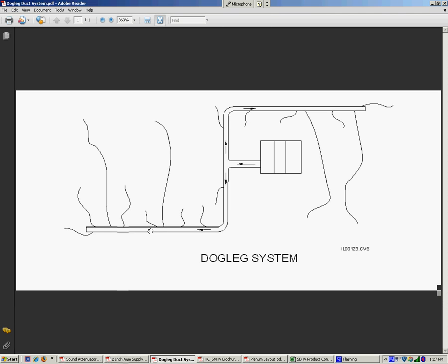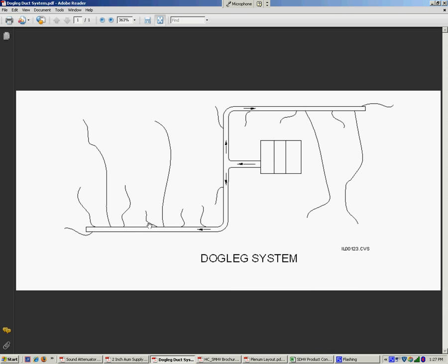For example, a short run, in this case, say a three-foot run of two-inch flexible duct, we can put out about 35 CFM, whereas on a 20-foot run of two-inch, we're only going to put out about 28 CFM. And we need to determine exactly how many CFM we're putting into the space to make sure we're getting the job done correctly.